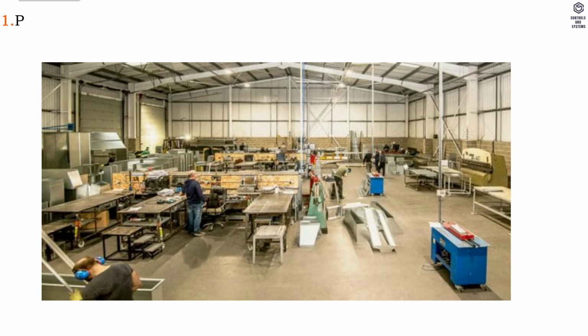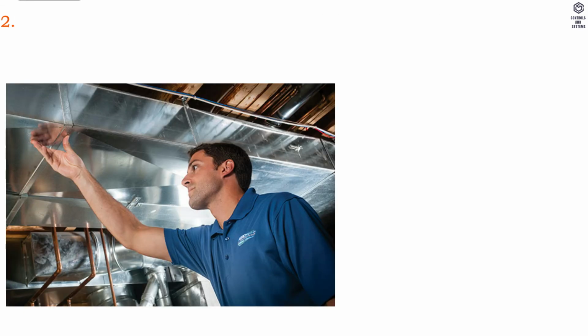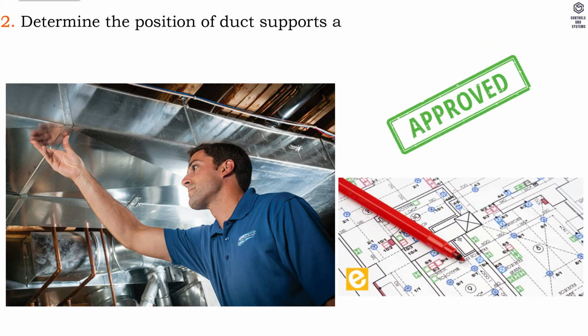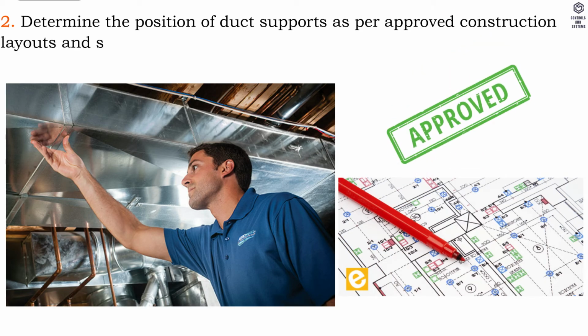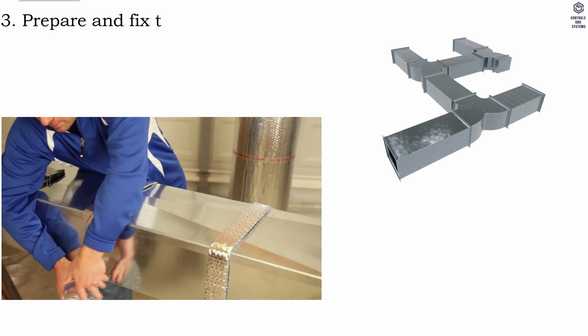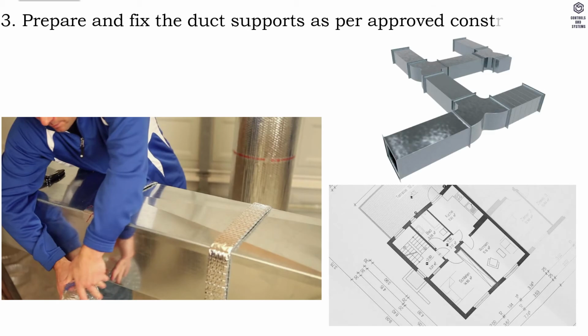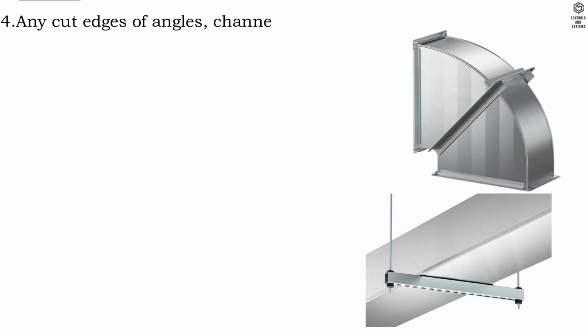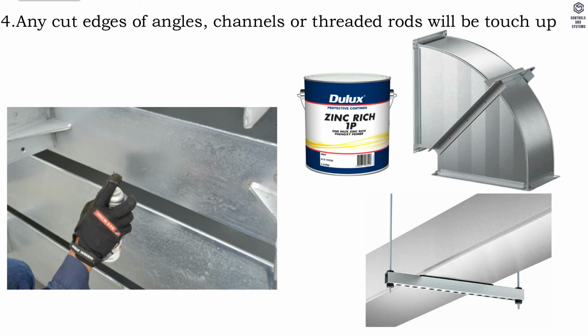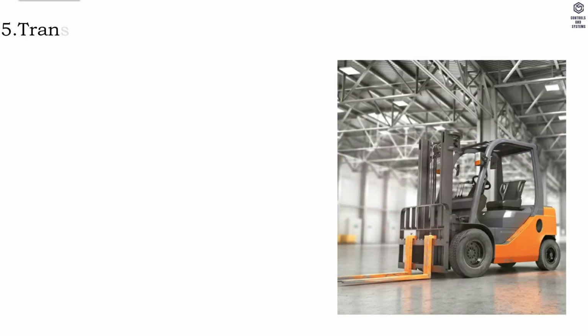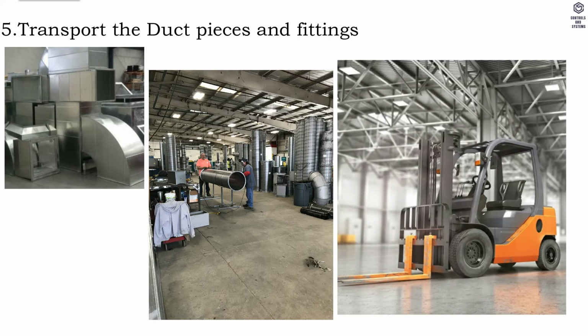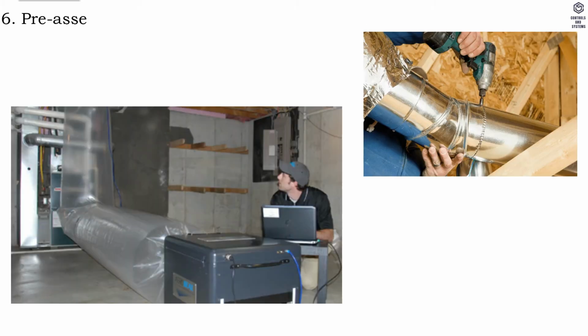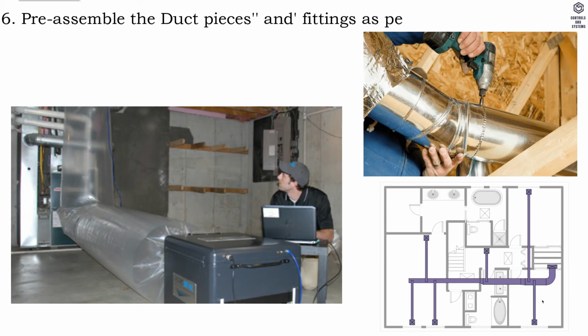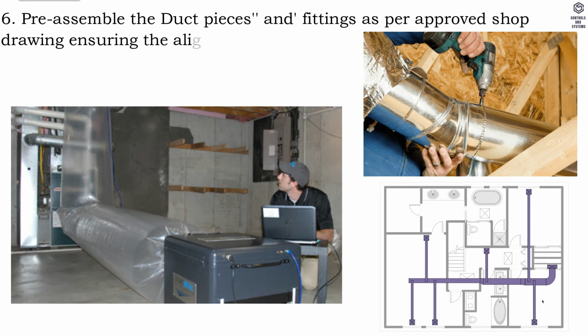Method of installation. 1. Prior to commencement of work, coordination will be done with other trades. 2. Determine the position of duct supports as per approved construction layouts and specification. 3. Prepare and fix the duct supports as per approved construction drawing and specification. 4. Any cut edges of angles, channels or threaded rods will be touched up with zinc-rich paint. 5. Transport the duct pieces and fittings to final location. 6. Pre-assemble the duct pieces and fittings as per approved shop drawing, ensuring the alignment.